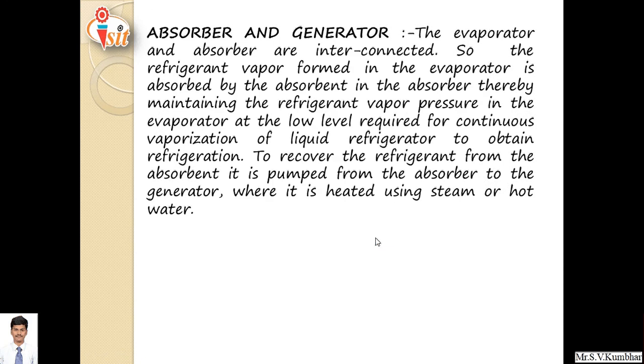The evaporator and absorber are interconnected. The refrigerant vapor formed in the evaporator is absorbed by the absorbent in the absorber, thereby maintaining the refrigerant vapor pressure in the evaporator at the low level required for continuous vaporization. To recover the refrigerant from the absorbent, the solution is pumped from the absorber to the generator, where it is heated using steam or hot water.